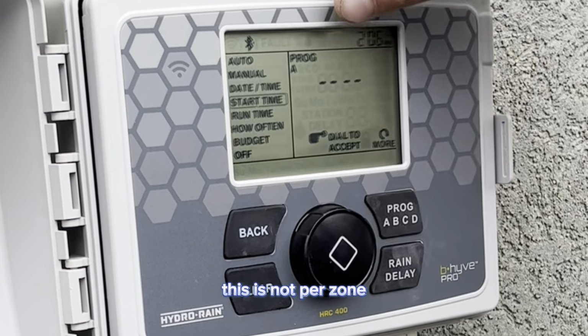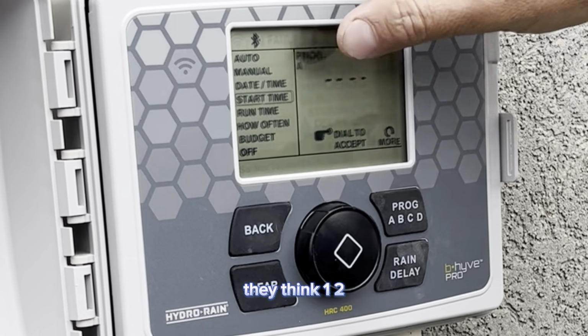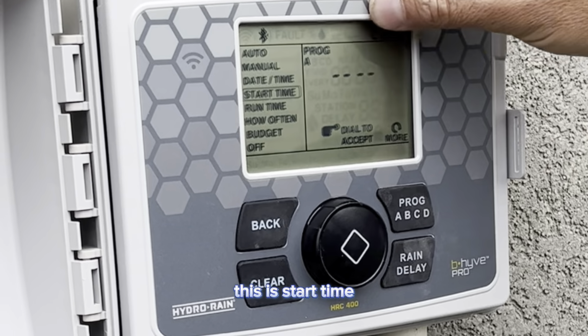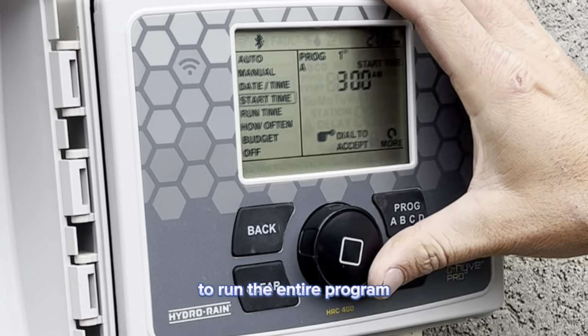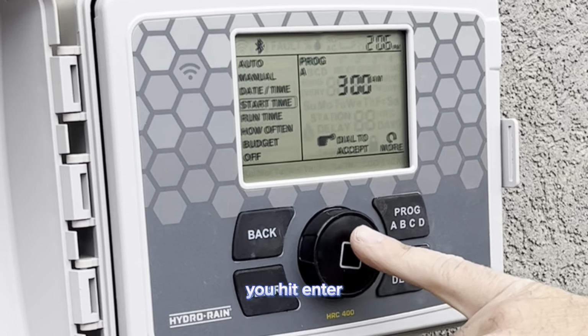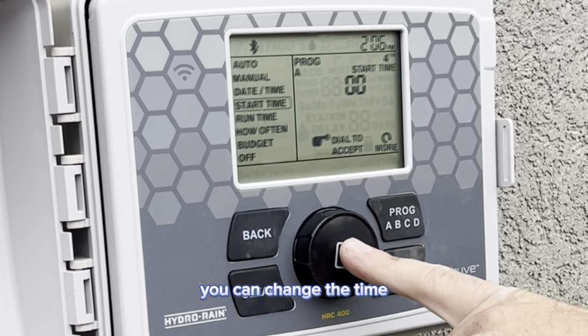This is not per zone. A lot of people mix this up. They think 1, 2, 3, 4 is each zone. This is start time to run the entire program. So if it's where you want it, you hit enter, it's going to rotate through. You can change the time.